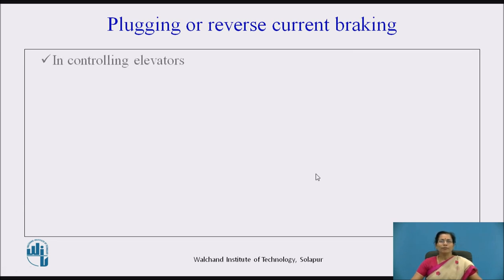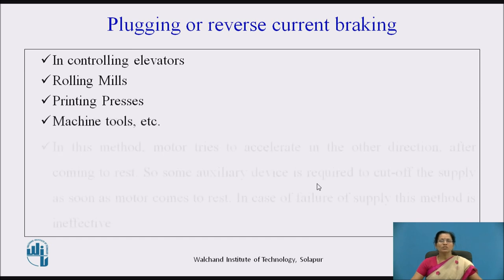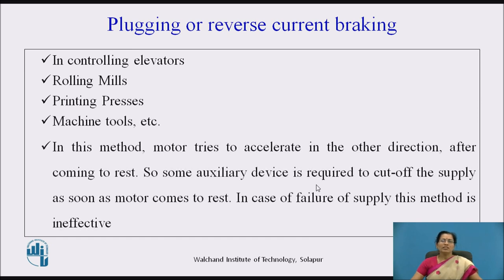Reverse current braking or plugging is used in controlling elevators, rolling mills, printing presses, and machine tools. However, in this method the motor tries to accelerate in the other direction after coming to rest, so an auxiliary device is required to cut off the supply as soon as the motor comes to rest. In case of failure of supply, this method is ineffective.